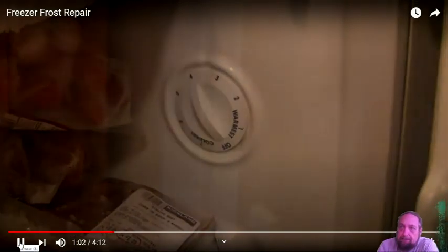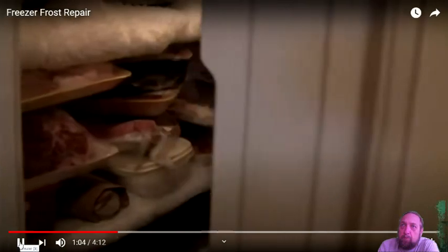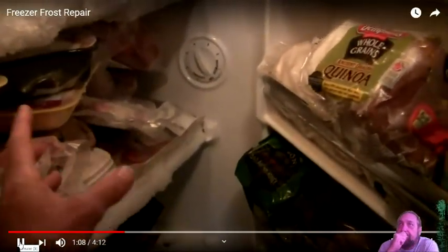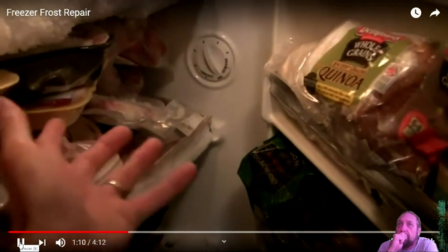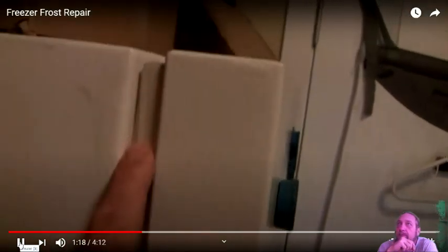No defrost cycle here. So we've clearly got a problem of warm air entering our freezer somehow. Now, one of the commonest problems is to have a piece of food that's pressed up against the door so it can't shut properly, but this door seems to shut just fine. The second thing we look for is we look for this strip here to see if there's any gap that allows air to get inside. And let's just follow this down here.